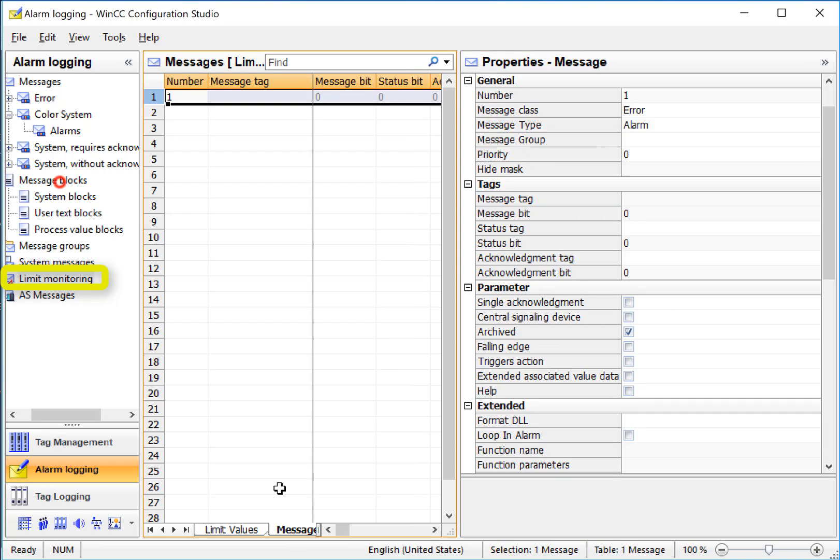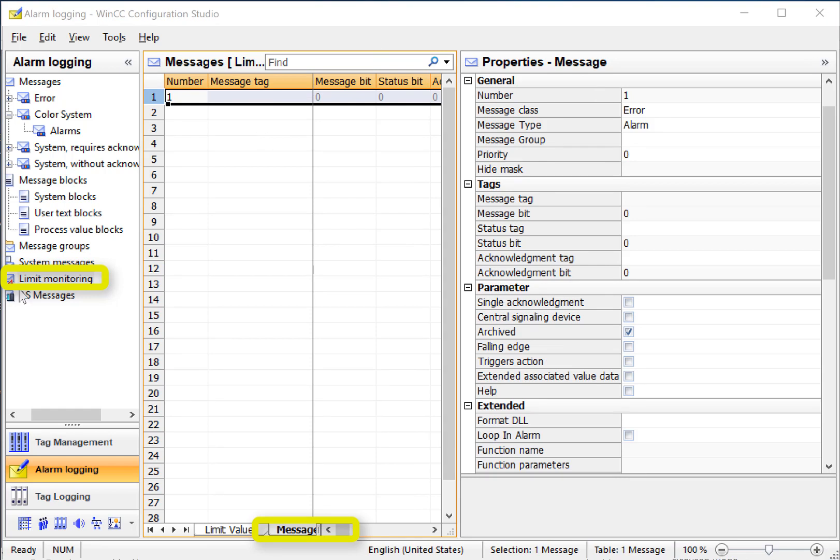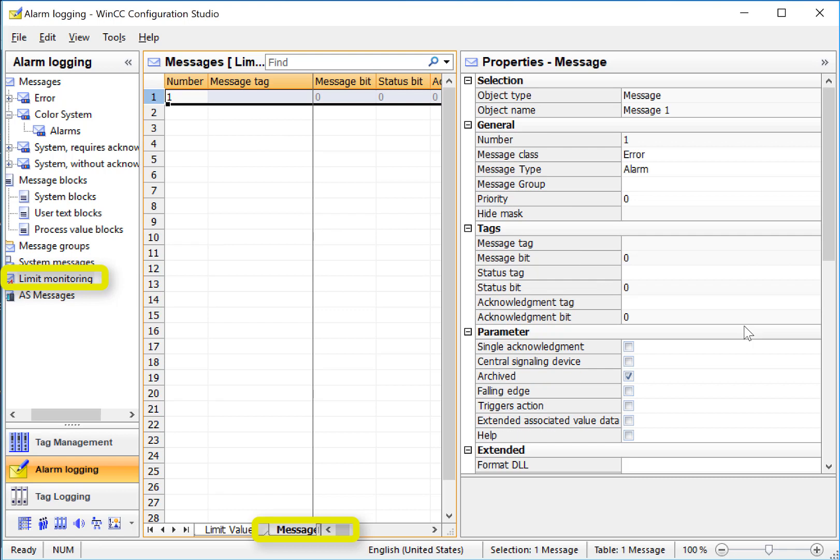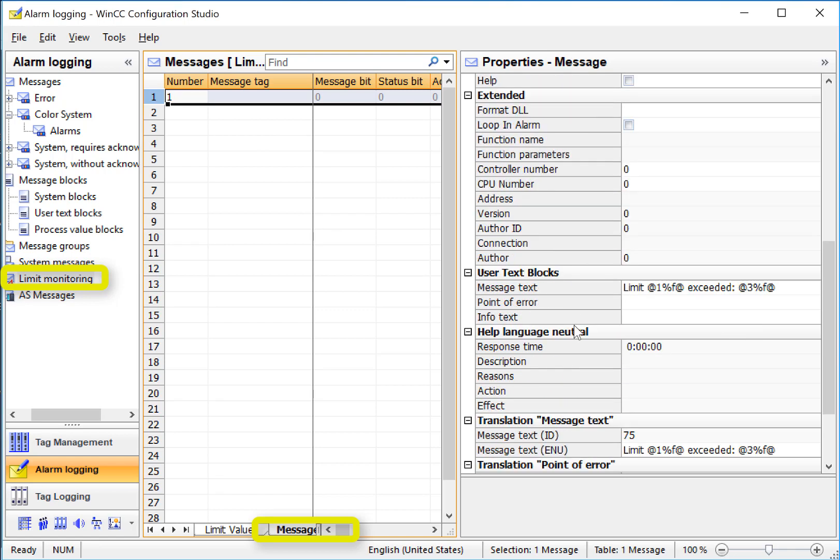And we can go to our messages tab and look at that. Notice that there's no message tag here. That's OK because the analog limit monitoring engine is taking care of that. If we scroll down, you can see that it's created our message text for us. And it's going to input the proper values here, the limit that it exceeded and what its actual value is.